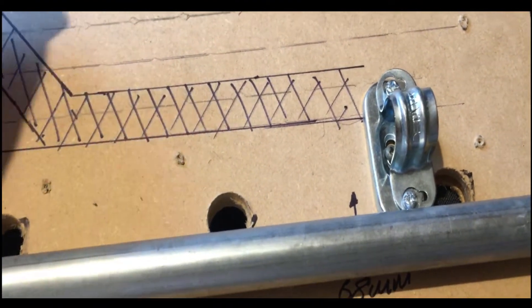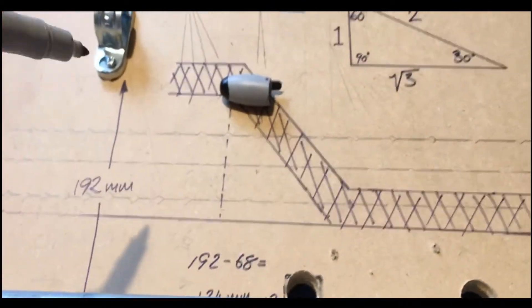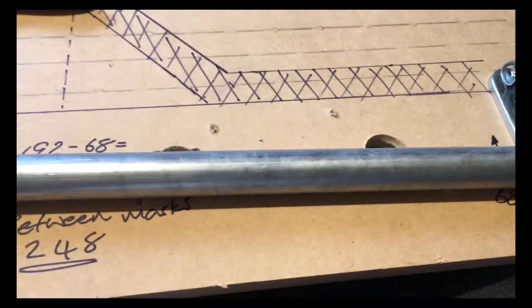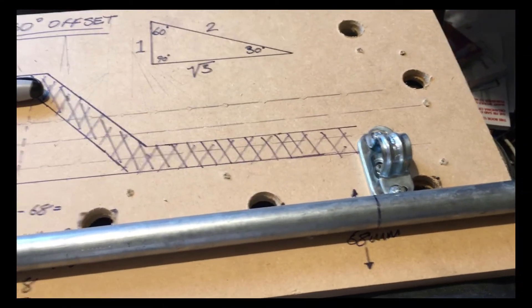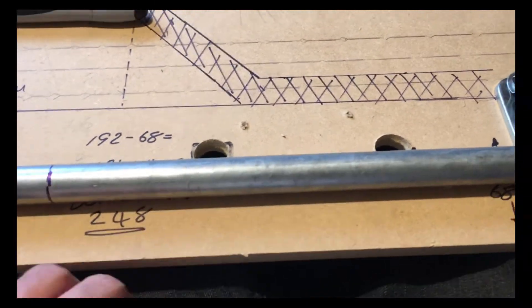Then hopefully after bending it at a 30-degree angle, I should be able to get my set and it should fit into this template here. So I'll try that. Okay, so I've marked my conduit here at 248 millimeters.